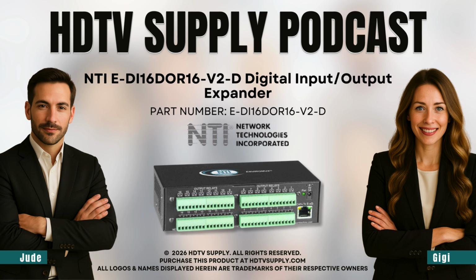You connect this thing with a single CAT5 cable, and you instantly get 16 more digital inputs for sensors. And not just inputs. And you get 16 digital relay outputs for control. So you're turning one connection point into 32 endpoints. That completely changes your monitoring landscape. Let's start with the inputs. What is the V2D actually reading?